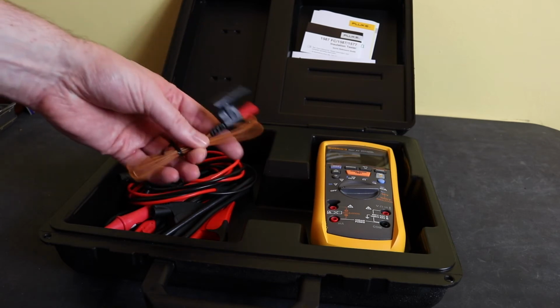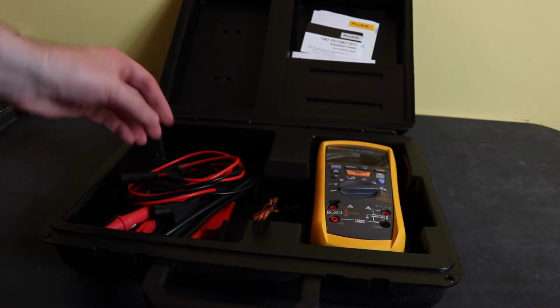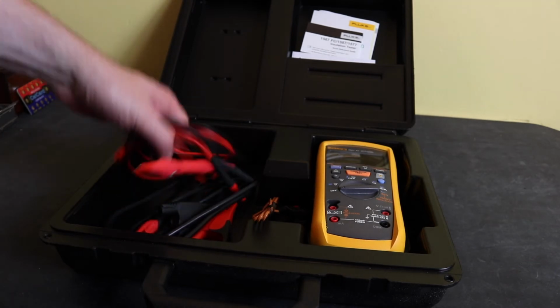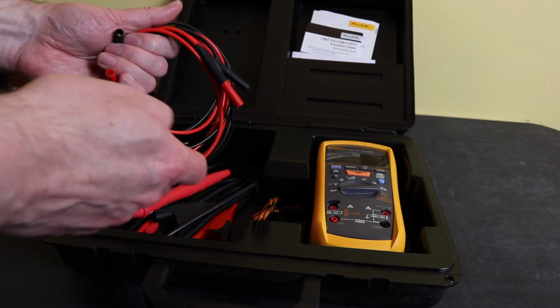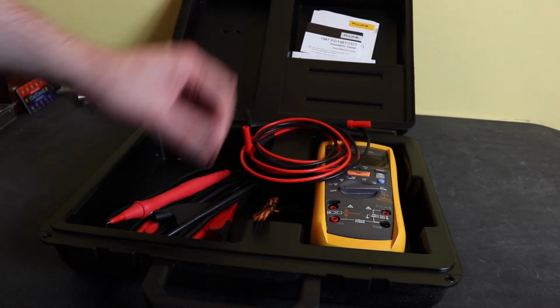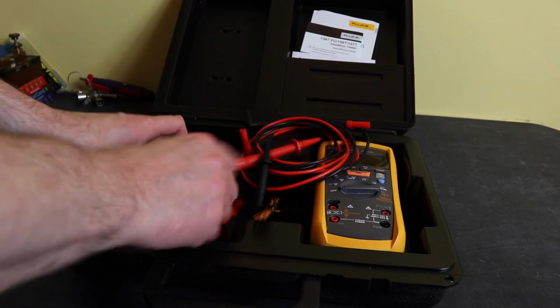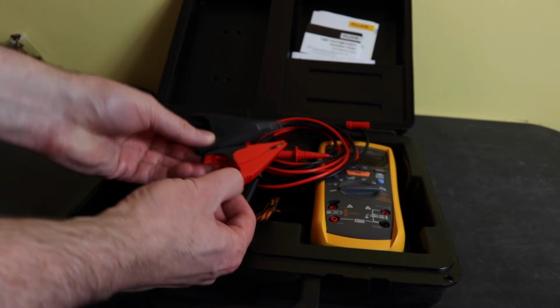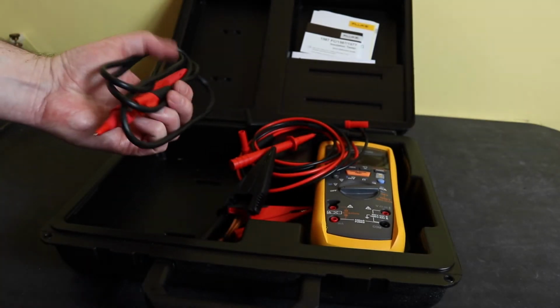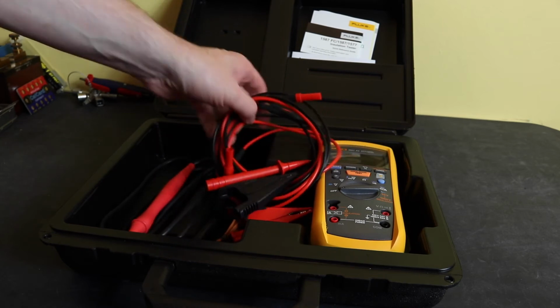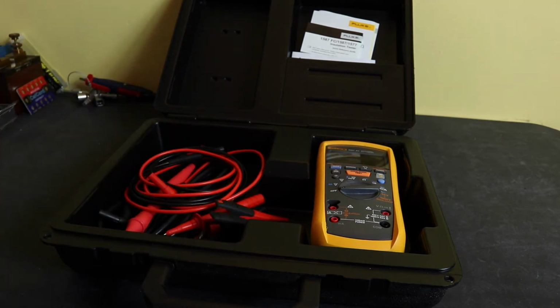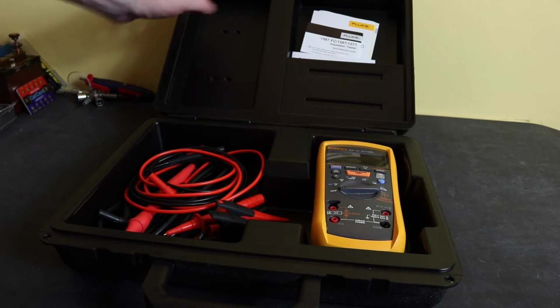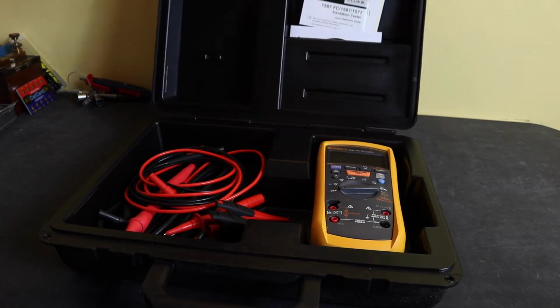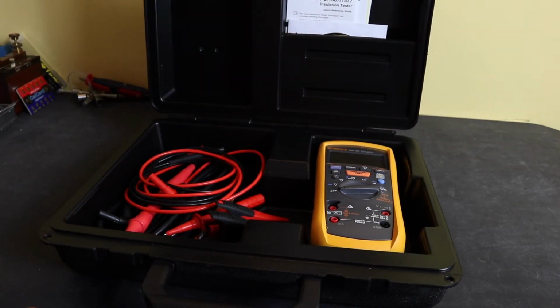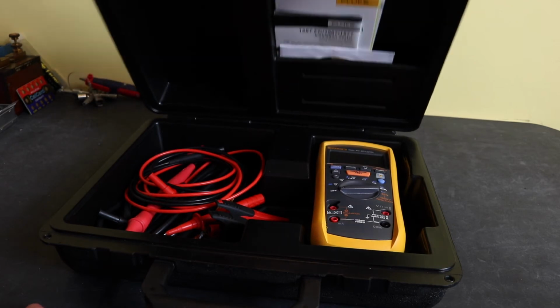The accessories you get are a K-type thermocouple for the temperature measurements, a set of silicon test leads with 4mm connectors on them, a set of probes to match, a set of croc clips to match, and the remote probe, all housed in a pretty robust blow moulded case. Plenty of room for other bits and pieces that you may want to stick in there, and a little instrumentation pocket up at the top here that you can house instructions, calibration cert, etc.